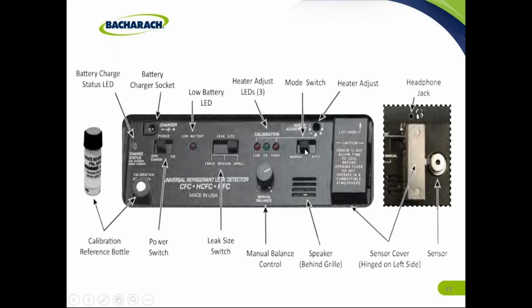In the manual switch, you have a manual balance control here that you would use with it. And you will have a tick rate of 1 to 3 ticks per second, tick, tick, tick. If it's a lot higher than that, then you want to start turning this down till you get that 2 to 3 tick rate per second. As you get closer to the leak with your probe, it'll start ticking faster. Then once again, you adjust this down. A lot of leak detectors have a thumb wheel on them, whether combustible gas or refrigerant leak detectors, and you do that same thing, and that's how you go find a leak.